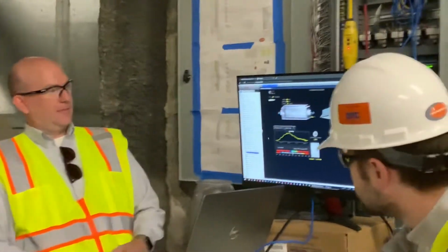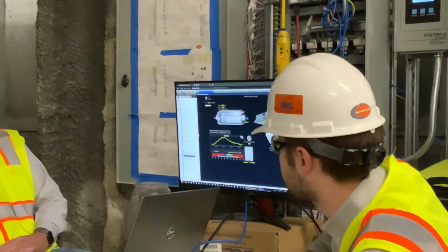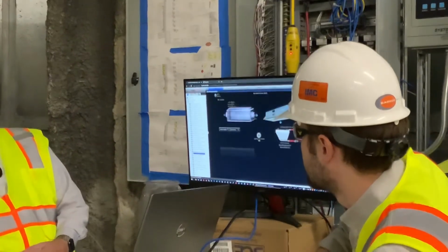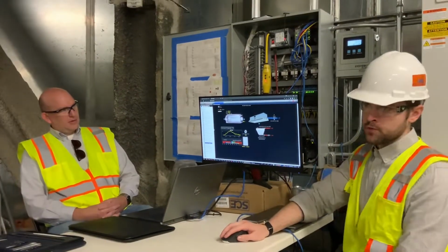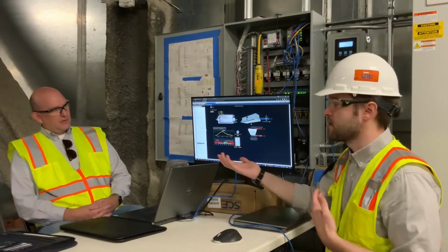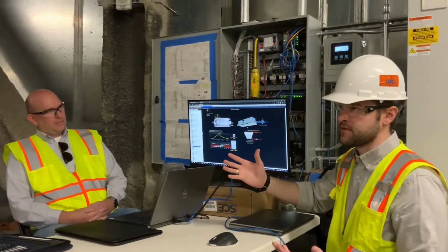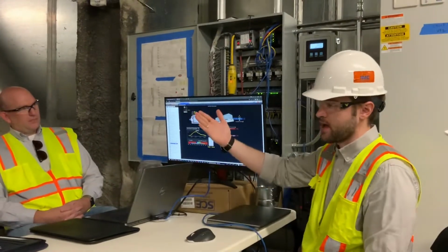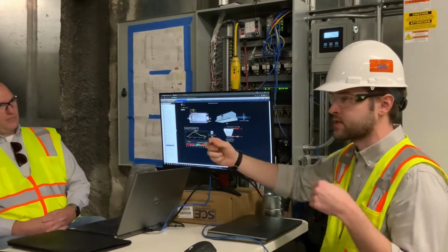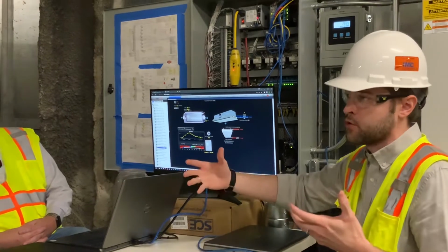So in this room in particular, we've actually got multiple VAVs in one room. In that case, the way our VAV controllers work, they basically bolt right onto the side of the VAV. So that means if you have a room with multiple VAVs, usually we'll have a controller on each, and then we network the information for that lab or for that room between the controllers.